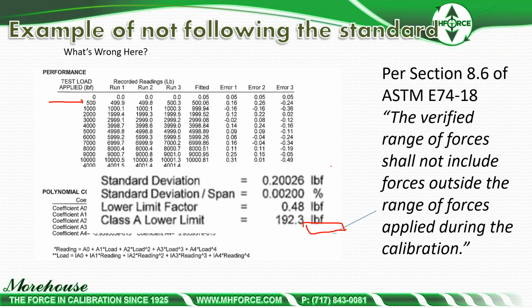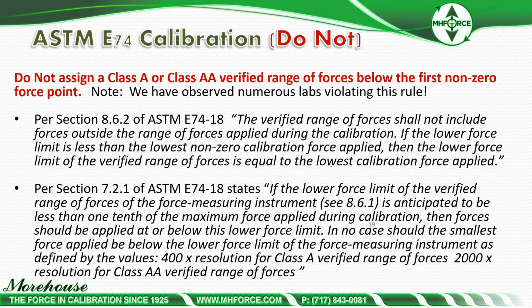And there you can see in more detail the standard deviation, lower limit factor 0.48, 192. Since the first force point was the first non-zero, remember 400 times the resolution, or 2000 times the resolution. Since the lowest point was 500, you cannot use this instrument below 500 pounds. What else do we see happen? Do not assign a Class A verified range below the first non-zero force point. They're the two sections, 8.6.2 and 7.2.1.